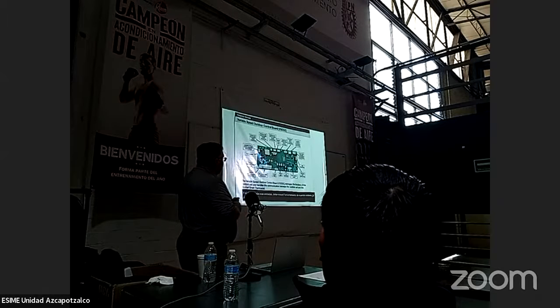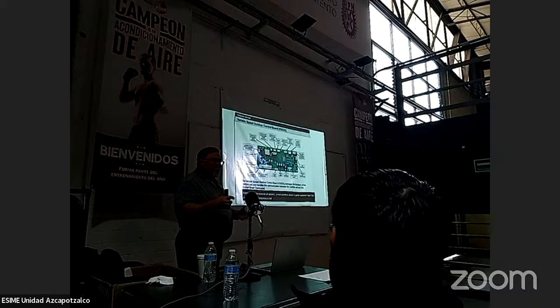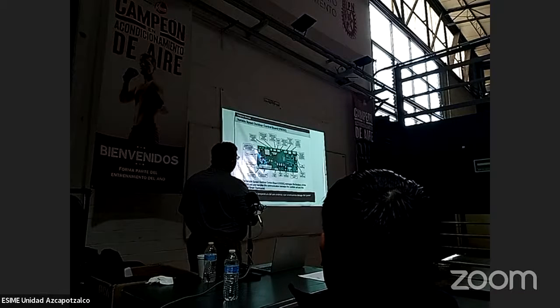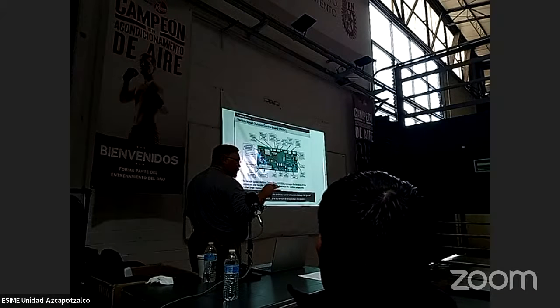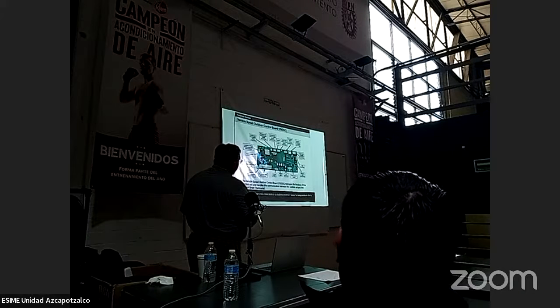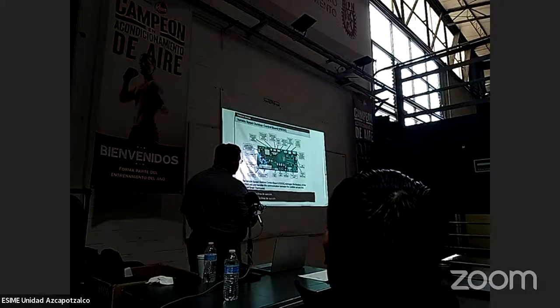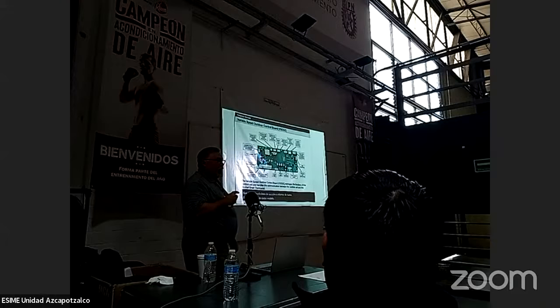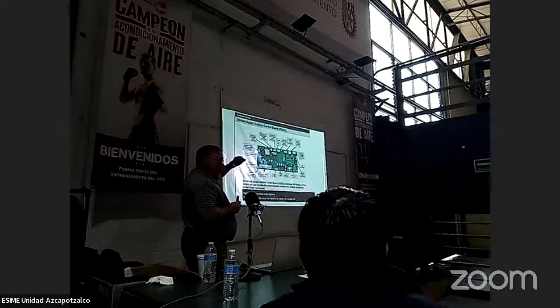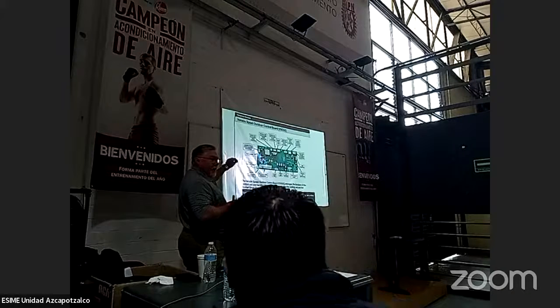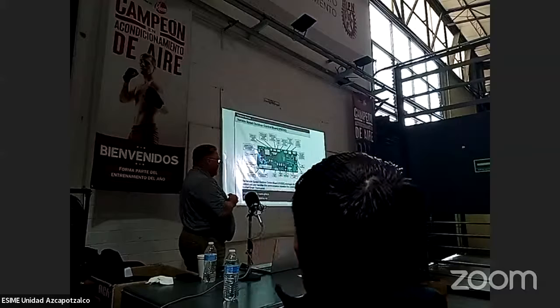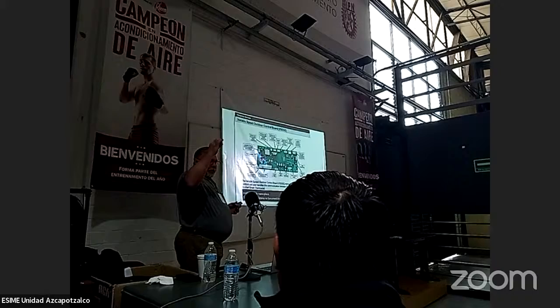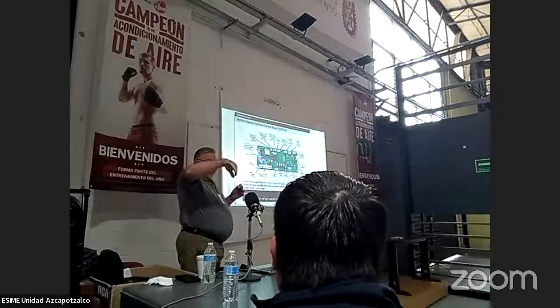Now, this is what the board looks like, and this is kind of giving you an idea of where everything connects. So if you're looking at the board, we'll start at the top right here. This is your outdoor air temperature sensor, which is located underneath the electrical panel on the outdoor unit. You have your coil temperature sensor connection, which is connected to your outdoor coil. You have your suction line temperature sensor connection, which connects to the suction line and it reports back. This is your model data card right here. If you change this board, you have to make sure that you pull that model data card off the old board, put it back on the new board. If you do not do that, the system will not operate. Okay, it's imperative. They even have that card tethered to the outdoor unit, so when you take it off, you have to remove it. And it just dangles there, so you remember to put it back.